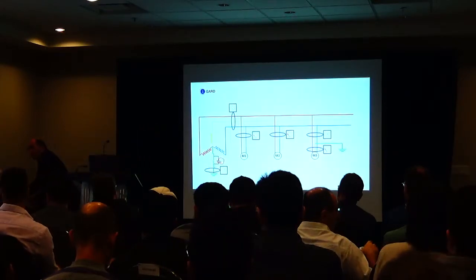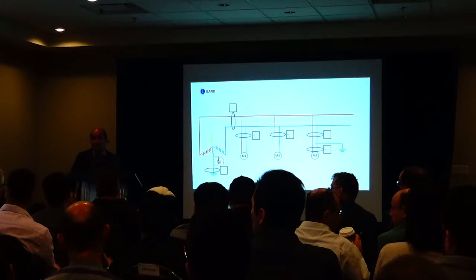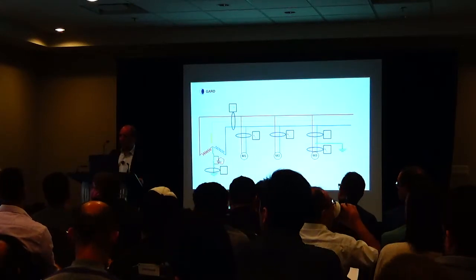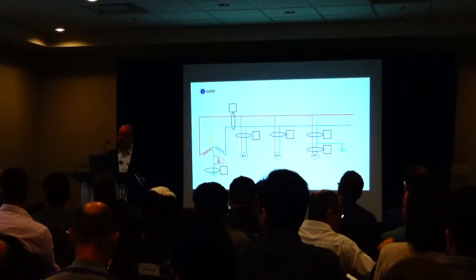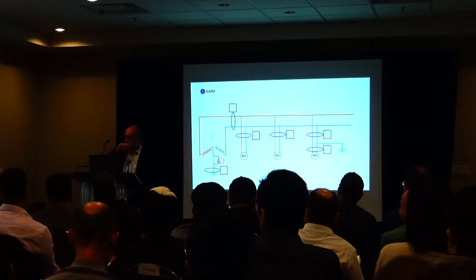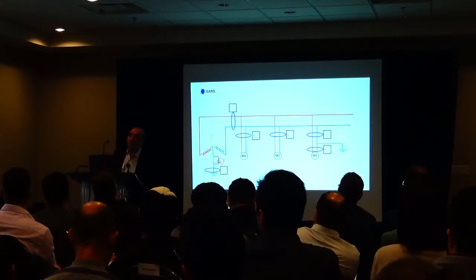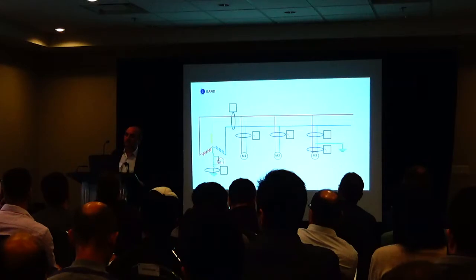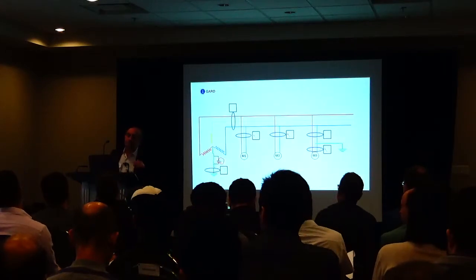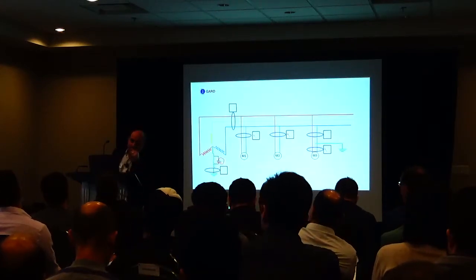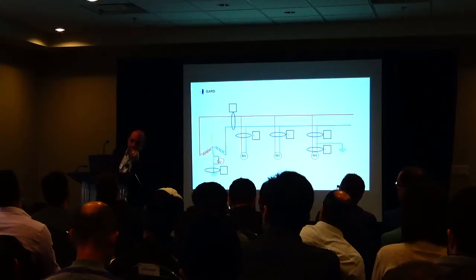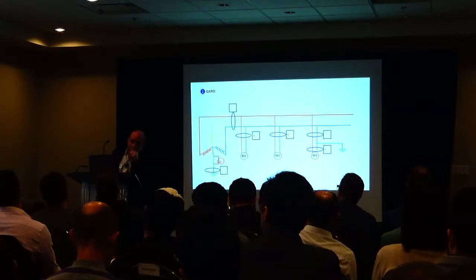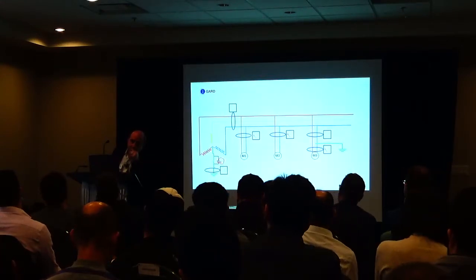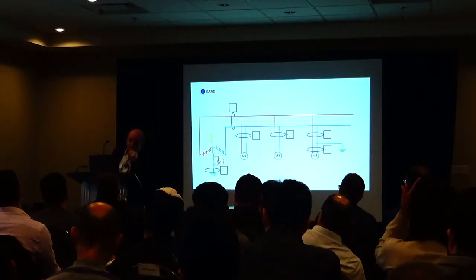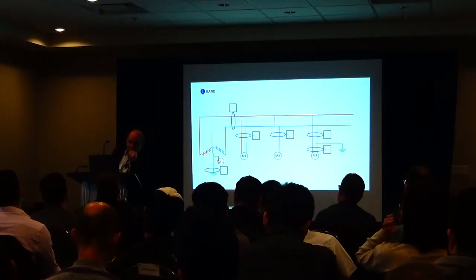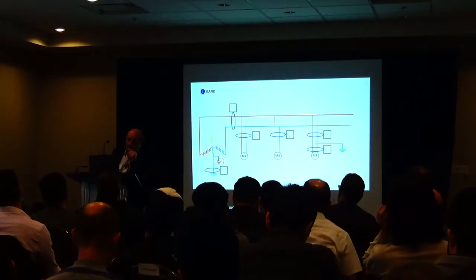So if you did want to convert over to an ungrounded system. To an ungrounded? No, not ungrounded. Sorry, a resistance grounded system. Yeah. There's already a system in place. They're already using the 347 for the lighting there. You want to then have it as a resistance grounded system. You've got to put in place a whole bunch of 600 to 347 transformers in order to continue providing that 347 where you need it. Right?